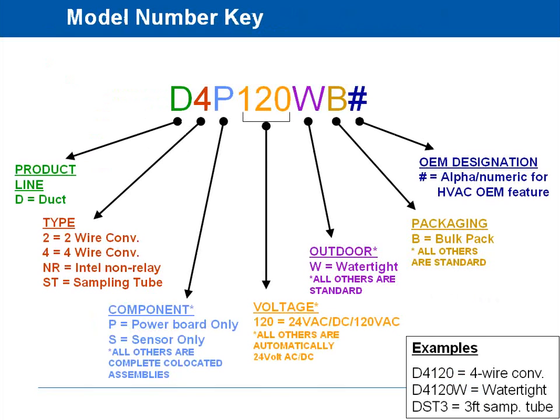The way the part numbers work, basically if it's a duct smoke detector, it starts with a D. Remember, System Sensor does make ceiling and wall devices, so D is for duct, which is what we're concerned with in the HVAC world. The next digit is whether you have a 2 or 4 wire. Almost everything nowadays is going to be a 4-wire detector, and that's the one we're stocking for the interlock wiring between these guys.